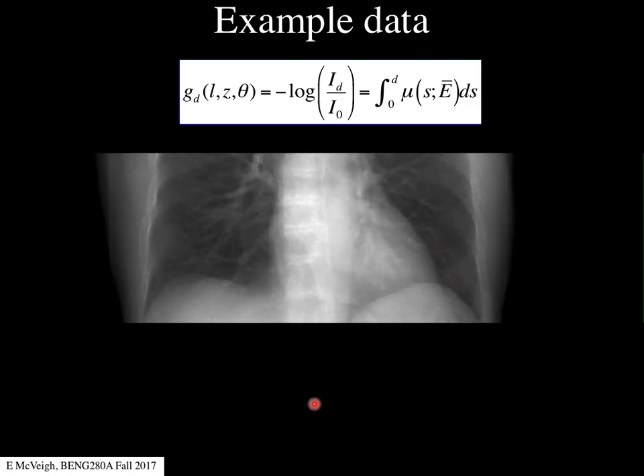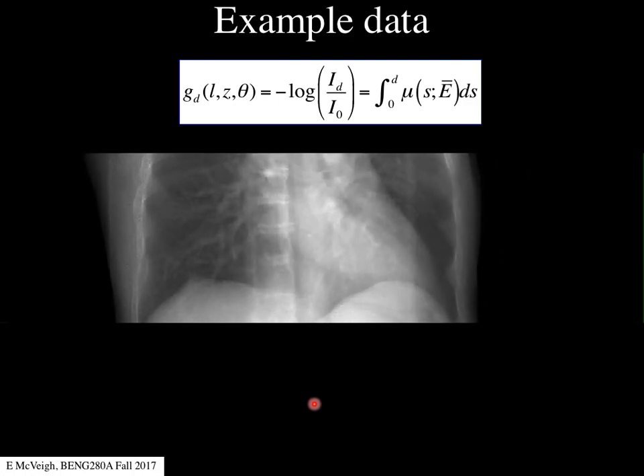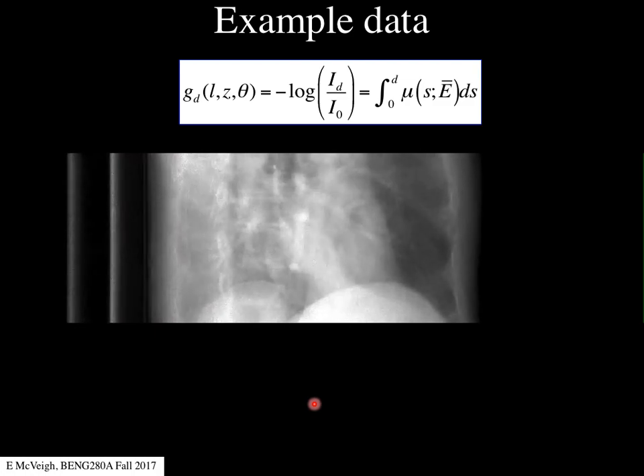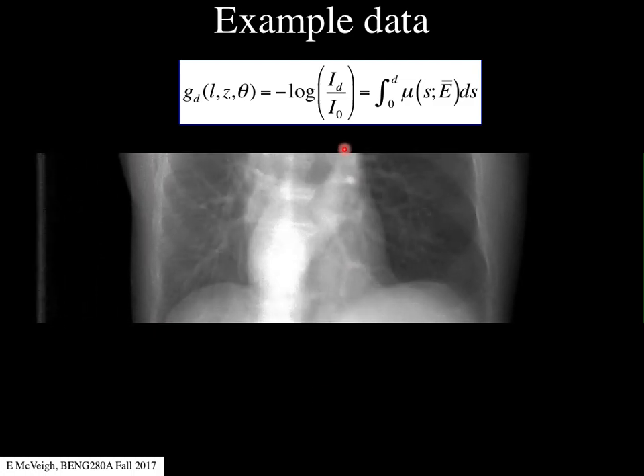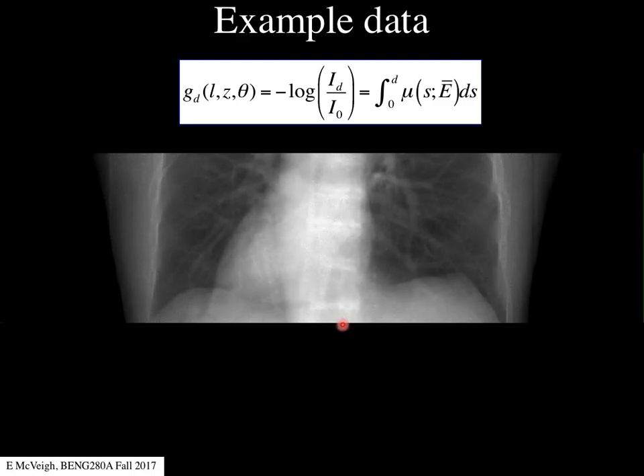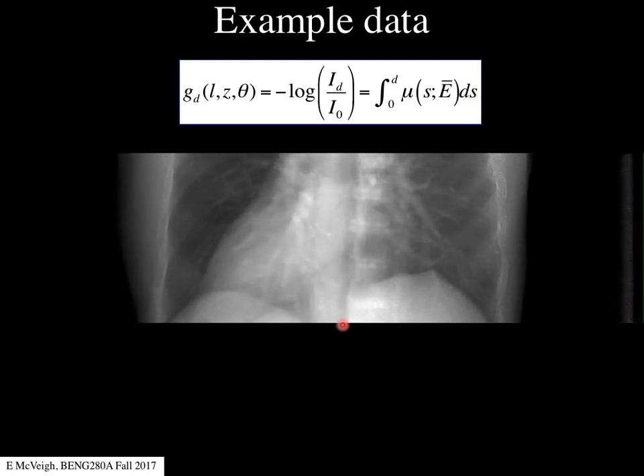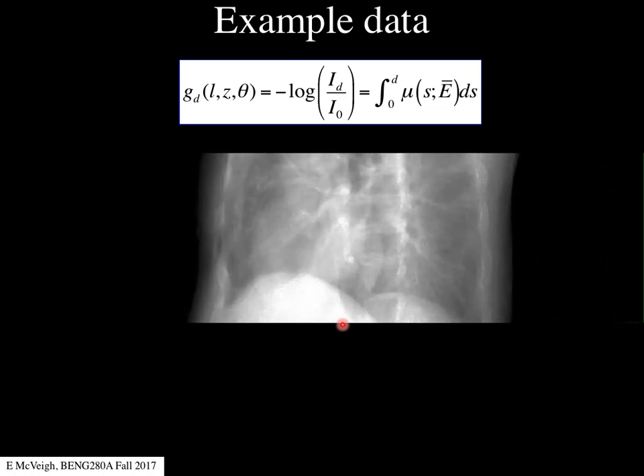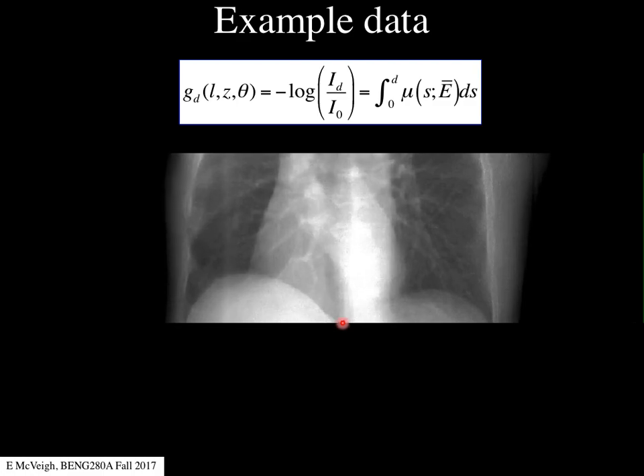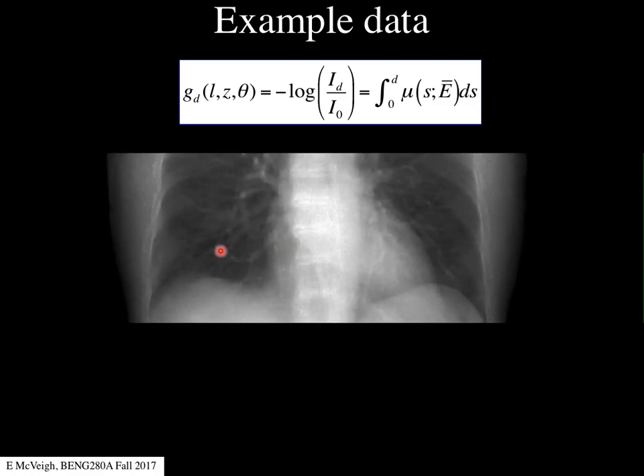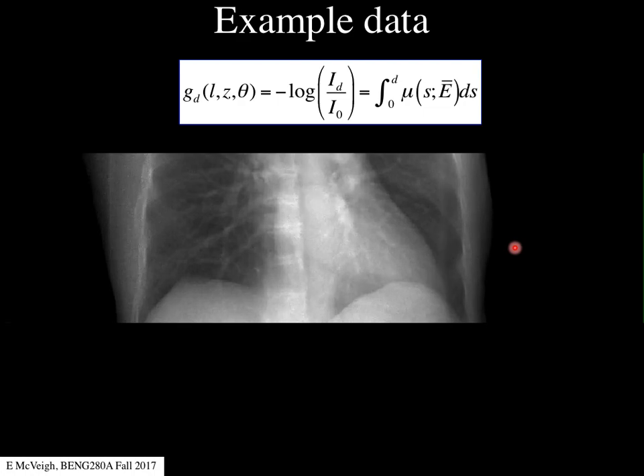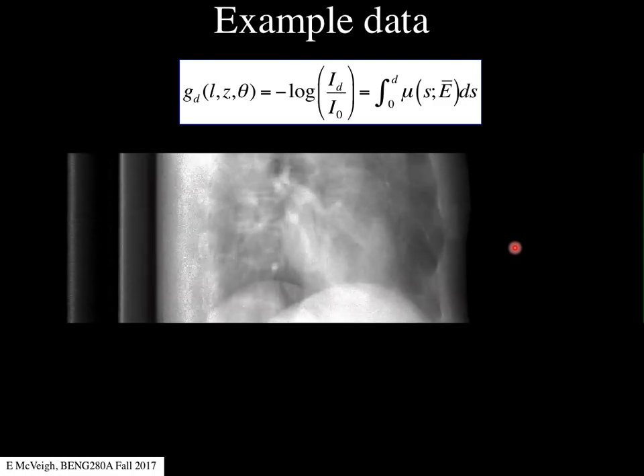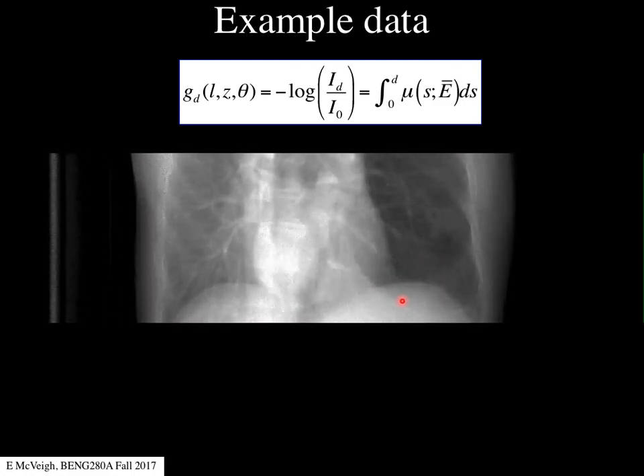Just to review from last lecture, this is what modern two-dimensional CT data looks like at different angles theta. The z direction is usually the slice direction. Most scanners now have at least 64 slices in that direction, going up to 320 on the Toshiba scanner. In the L direction there are about a thousand detectors, so the field of view is not square — it's a rectangle.